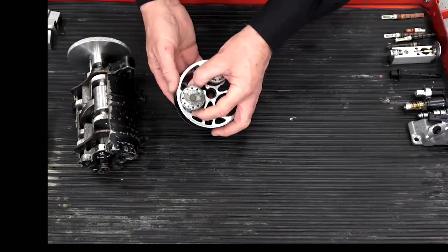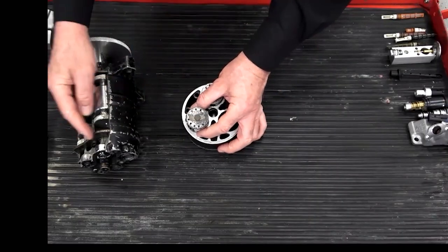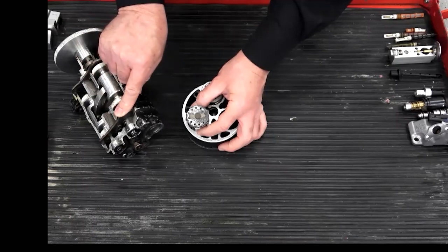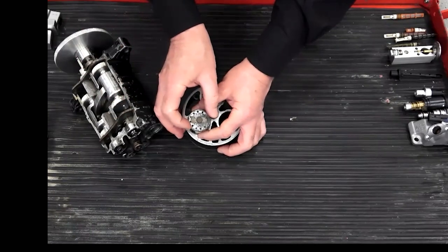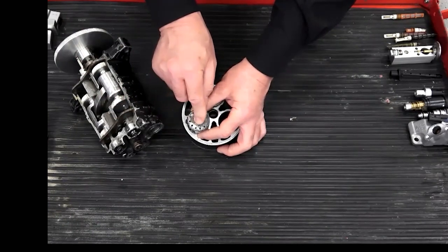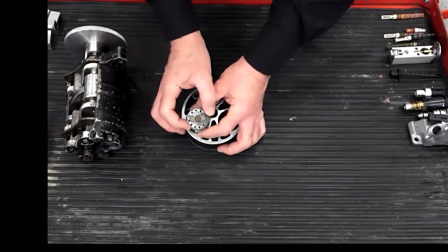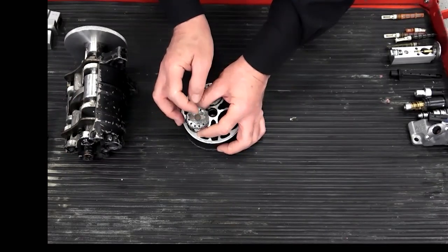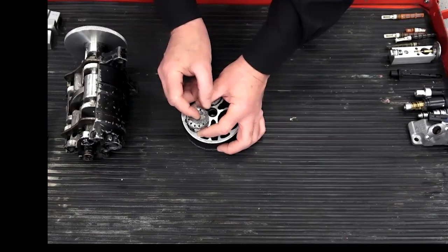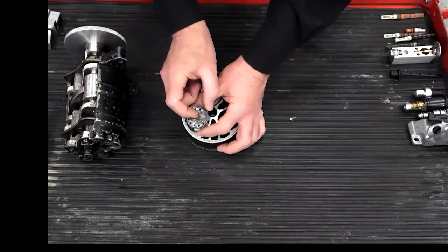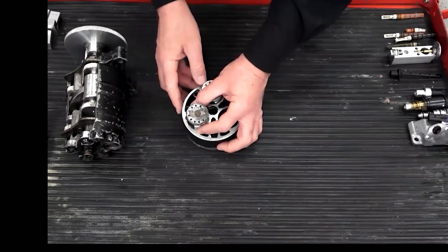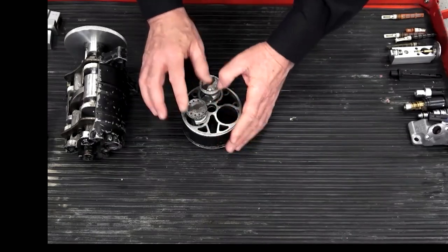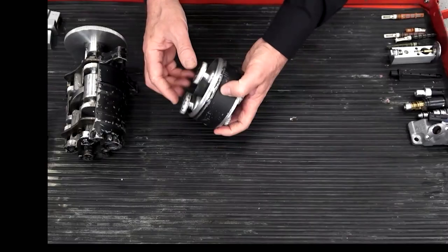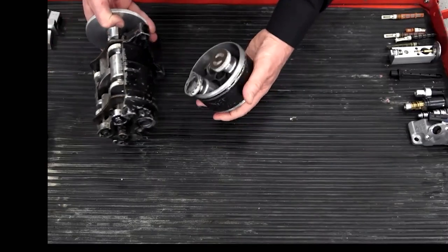That design compressor was redesigned, and instead of using a conventional valve plate like you can see here and here, they put the reed valves on top, riveted to the top of the piston. And the big problem with that was the radius. The reed valve has to bend between the center of the piston and the outside edge. It's a very short bending distance, and so this is the kind of compressor that's notorious for broken reed valves. And as I said, if your gauges are bouncing, it's a good possibility that you have a broken reed valve.